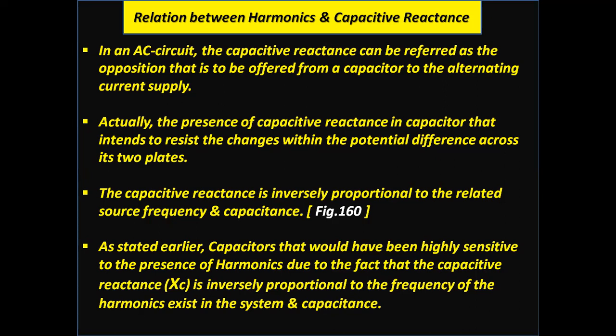The capacitive reactance is inversely proportional to the source frequency and the capacitance, figure 160. As stated earlier, capacitors are highly sensitive to the presence of harmonics, due to the fact that the capacitive reactance Xc is inversely proportional to the frequency of the harmonics existing in the system and the value of the capacitance.